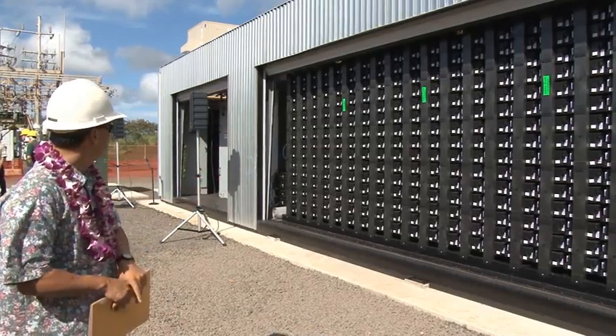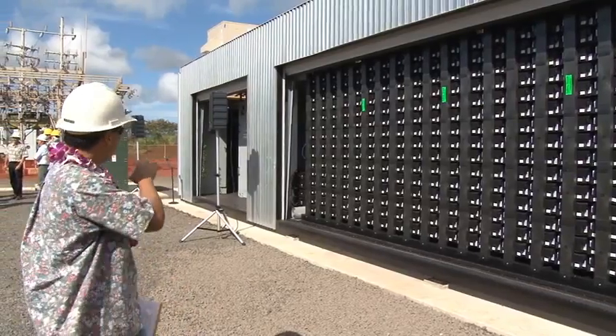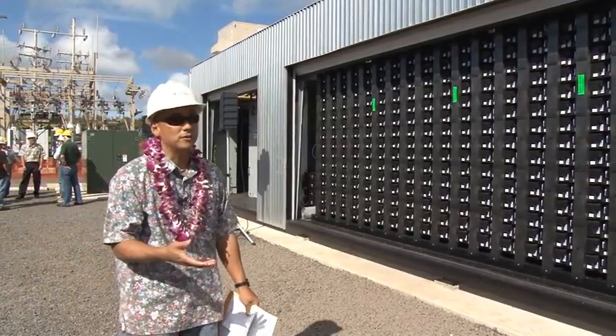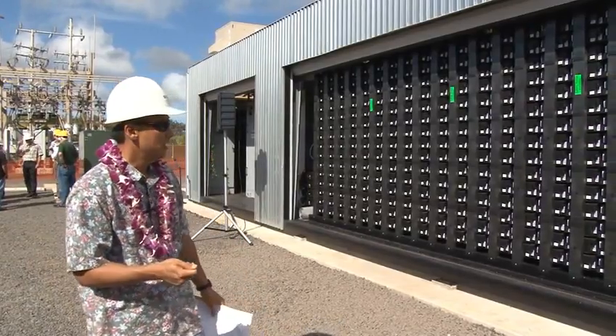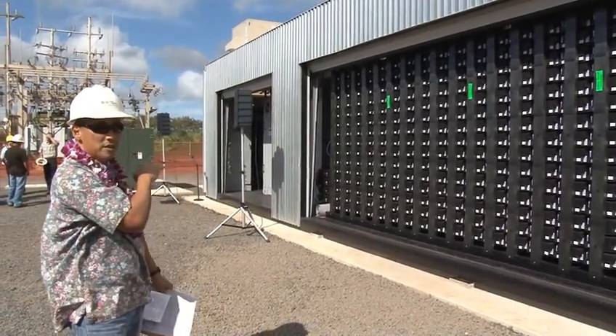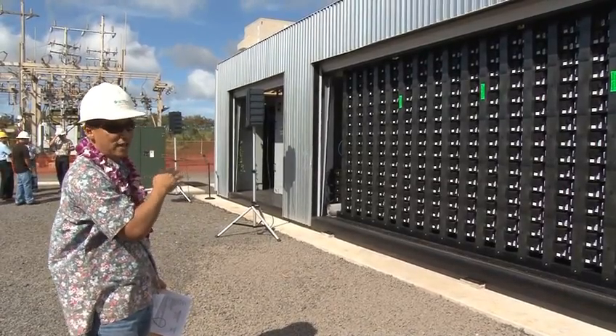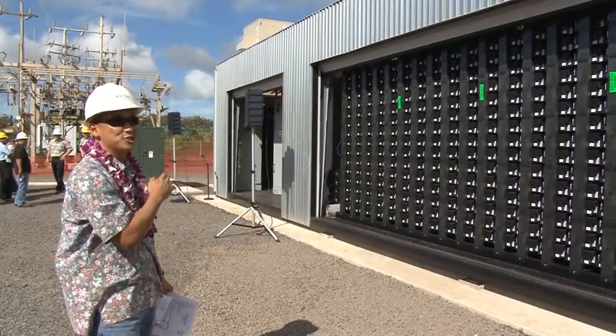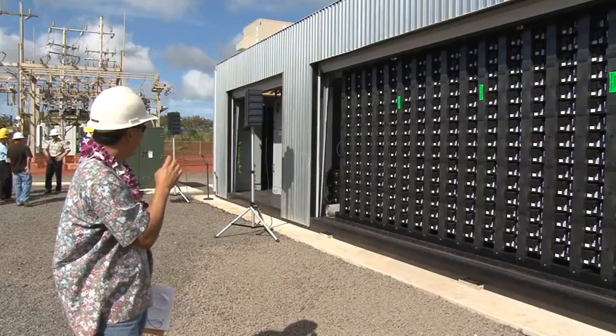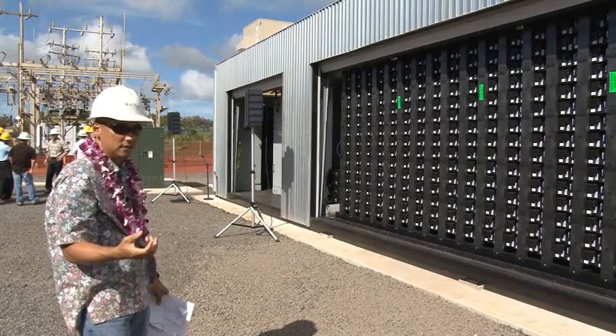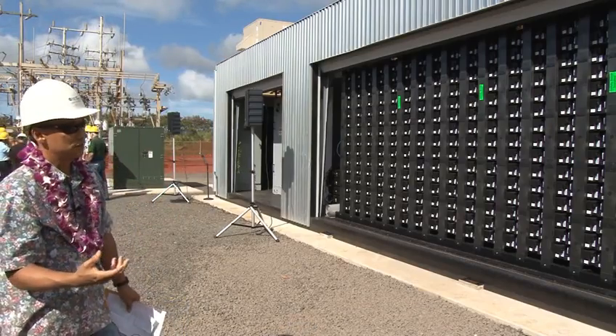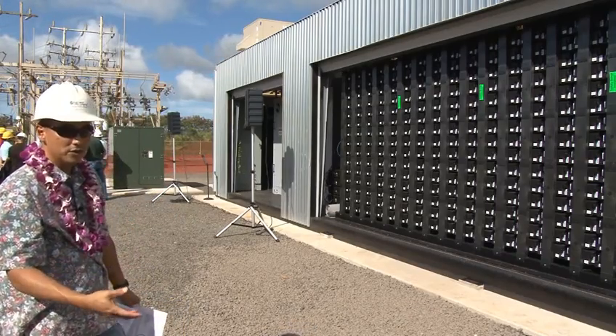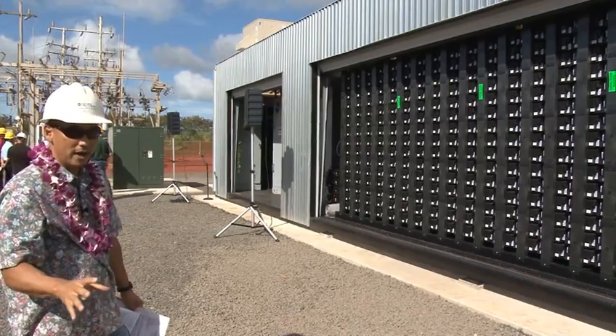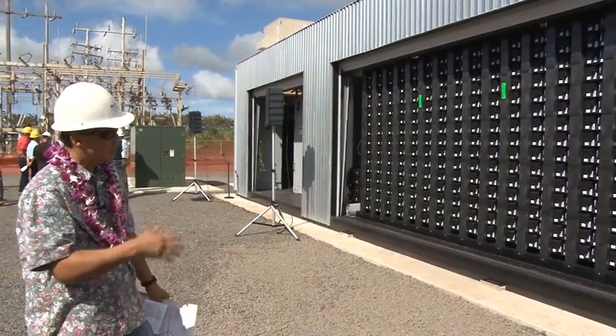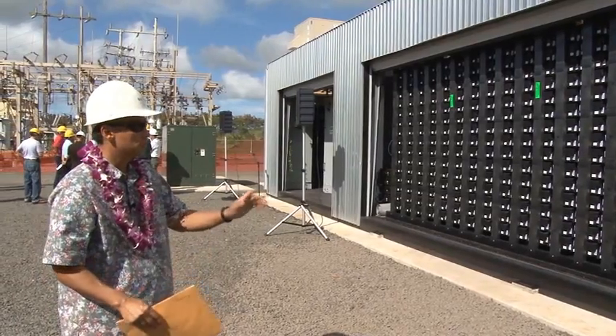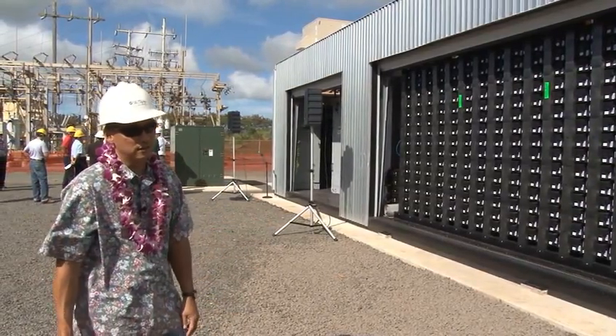What really makes a difference for managing the grid is the power conversion that converts DC, which is what batteries are. Everybody knows the Duracells are DC voltage. The power conversion, that's the part you hear humming there. And if it ever goes high, you know we just had an event, because that means it is discharging megawatts. That power conversion, a PCS, converts the DC to AC power. So it's almost like a UPS, where you have a battery backup in your computer in case you lose power and that battery just kicks in, but it converts it to your household voltage. Very similar, except a longer storage and a lot more power output, of course, to the utility.